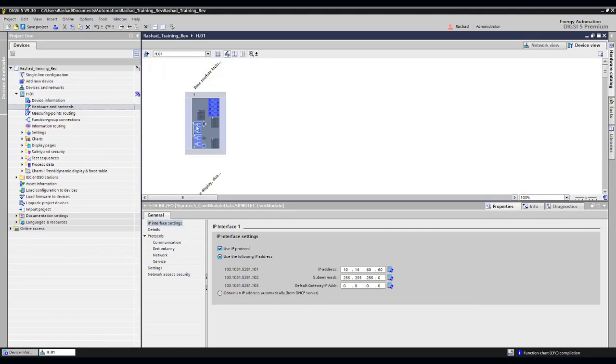As for me, the system interface, all I have to do is go and press on my card. And it will start telling you to set your three things: the IP address, the subnet mask, and the gateway address. Of course, the IP address depends on the IP address you have at the station, and naturally the last number here must be unique for each device. You can't have two devices on the same IP address.